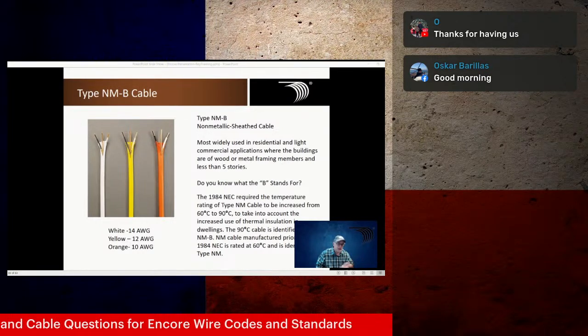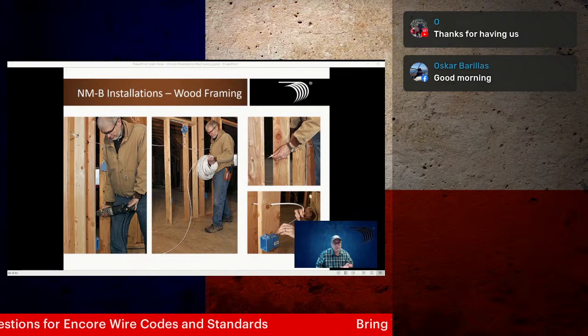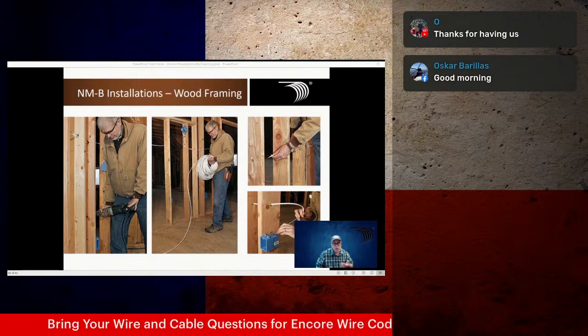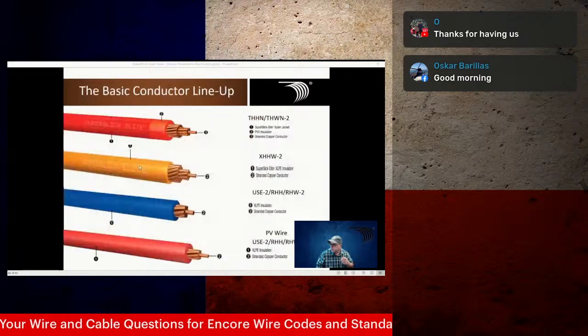So all of your non-metallic sheath cable today, the insulation on the conductors inside of it are going to be rated 90 degrees C. So this is just some examples of an installation using non-metallic sheath cable, boring those holes, maintaining 1.25 inches from the edge of the bored hole to the framing member on both sides, so that, you know, if you don't, then you've got to put nail plates up.